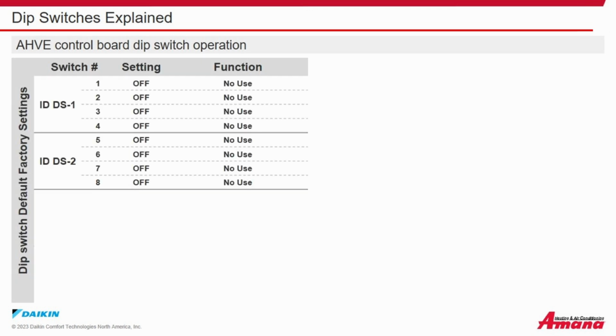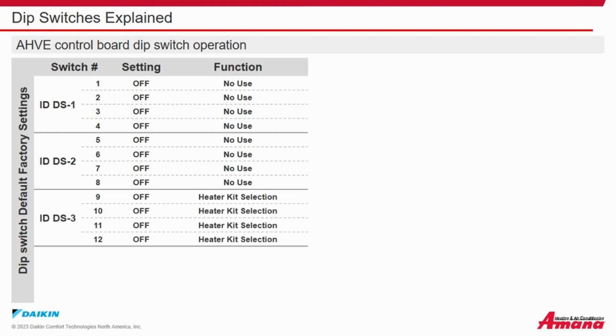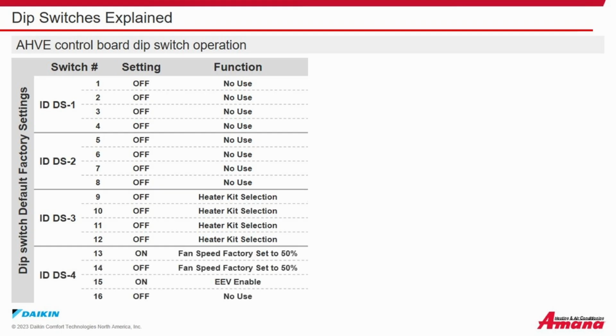Dip switch 1 and dip switch 2 are not used. Dip switch 3 is for heater kit selection. Dip switch 4, 13 on and 14 off, set the factory fan speed to 50%. 15 on enables the electronic expansion valve. 16 is not in use.